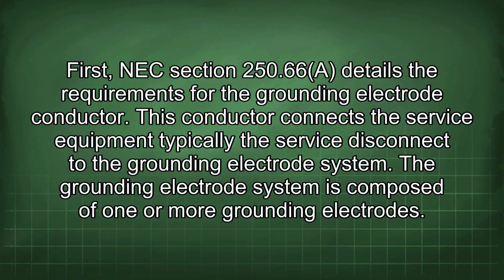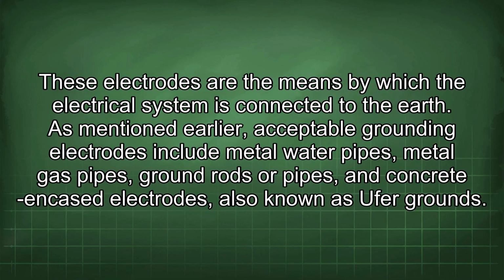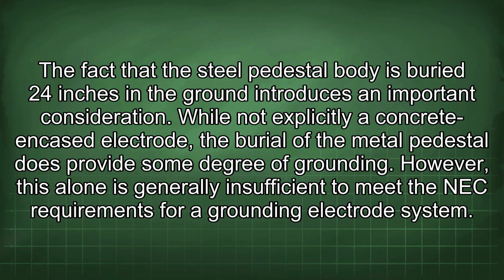The grounding electrode system is composed of one or more grounding electrodes. These electrodes are the means by which the electrical system is connected to the earth. As mentioned earlier, acceptable grounding electrodes include metal water pipes, metal gas pipes, ground rods or pipes, and concrete encased electrodes, also known as UFER ground. The fact that the steel pedestal body is buried 24 inches in the ground introduces an important consideration. While not explicitly a concrete encased electrode, the burial of the metal pedestal does provide some degree of grounding. However, this alone is generally insufficient to meet the NEC requirements for a grounding electrode system.